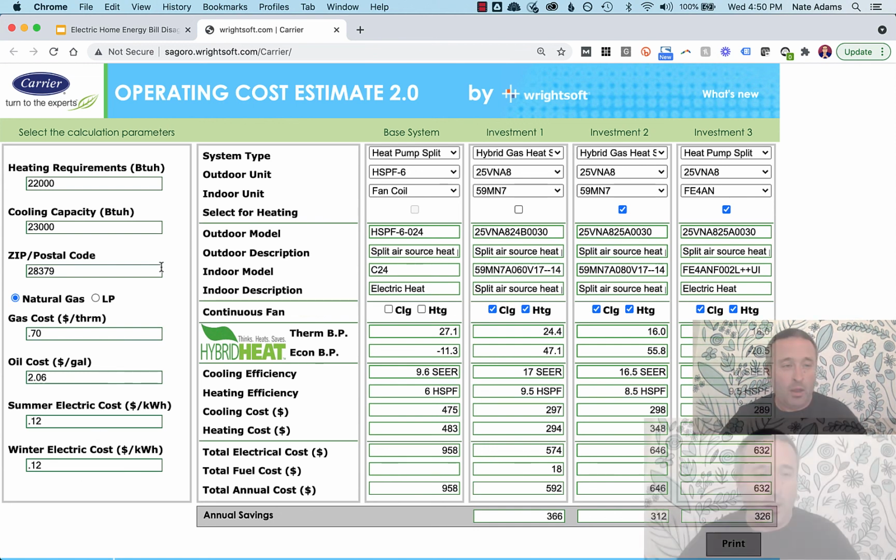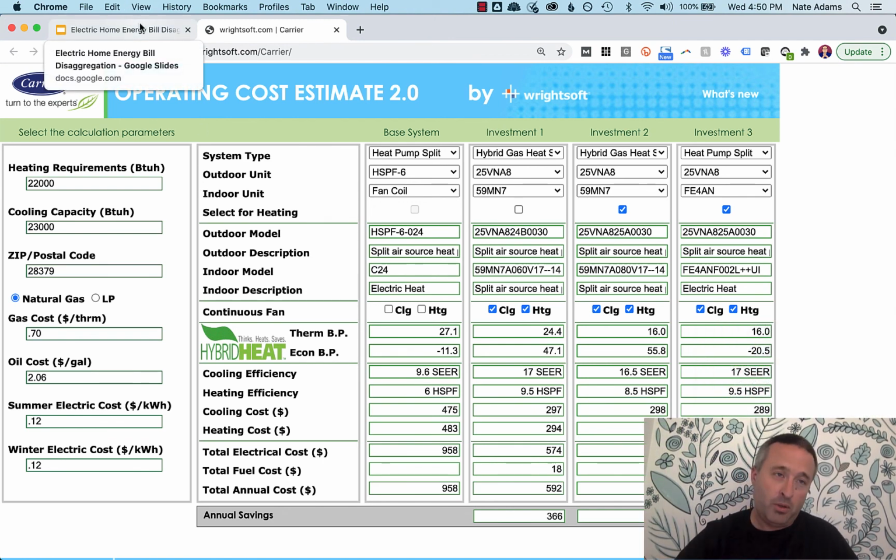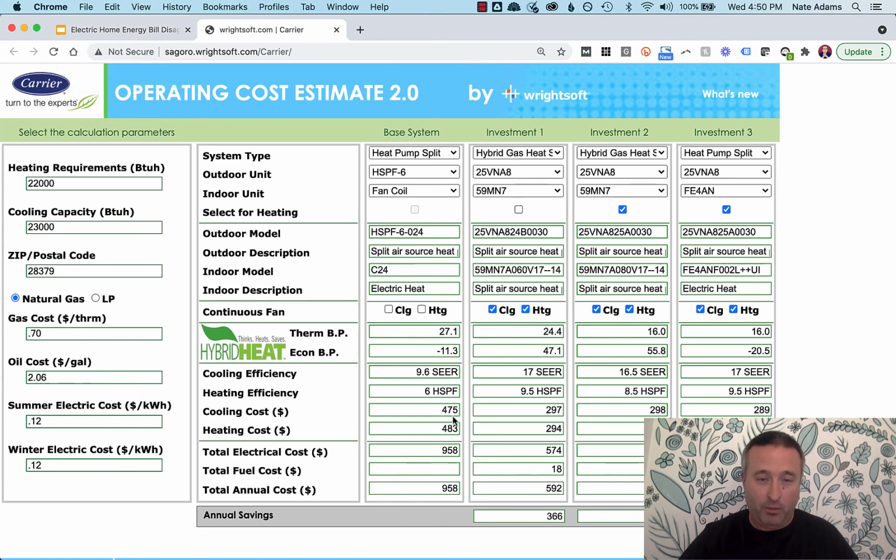So that is how we took monthly energy bills. We spit out that it's about 4,000 kilowatt hours per year for both heating and cooling. We could back into the heating and cooling loads, which are both right in the 2-ton ballpark. Normally you won't see this. Well, I guess it depends on what climate you're in. So if you're far south, your cooling will be greater.